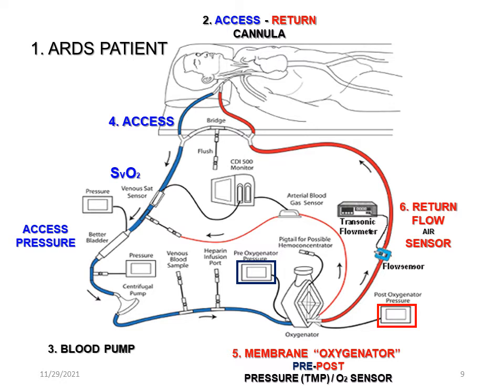Then we have the return flow, and before the blood goes back to the patient, resaturated, reoxygenated, eucarbic, flow is sensed. There's also an air detector, because we don't want to be putting air back into the patient. This will cause an air embolism. So there's a sensor. There's also a sensor for the saturation of oxygenated blood, called the post-saturation oxygenated blood. This is measured because if we compare the SVO2 and the SaO2, we would expect, if the oxygenator were working, that the SaO2 would be higher than the SVO2.